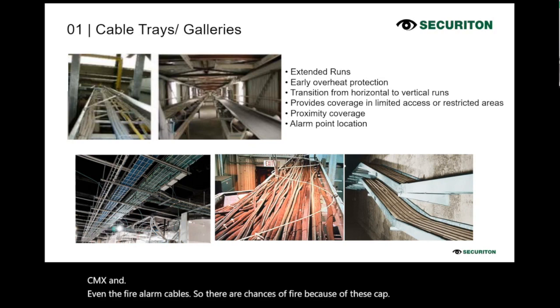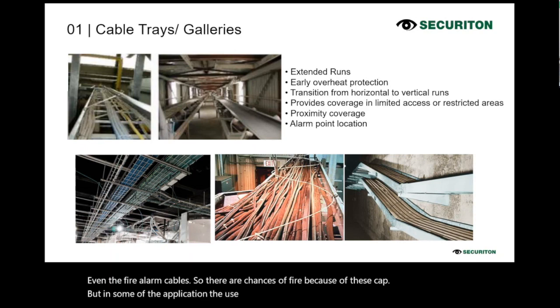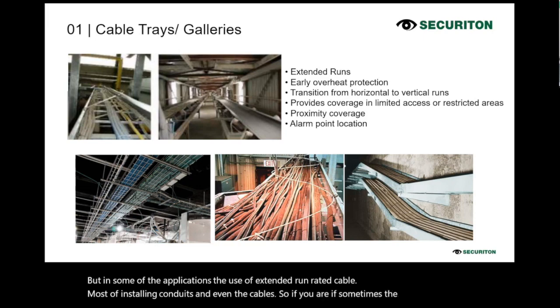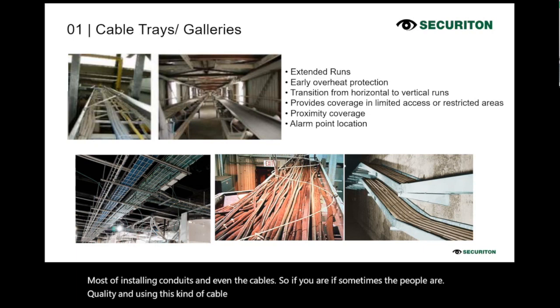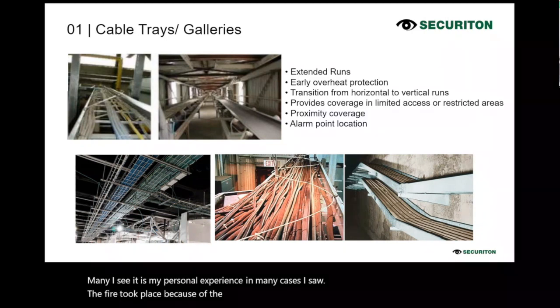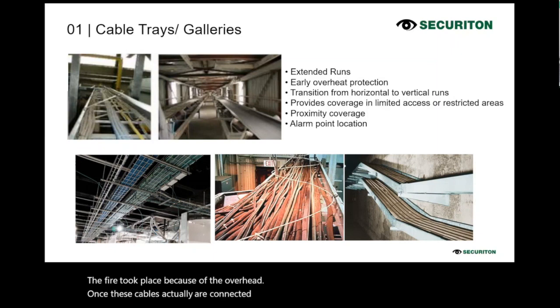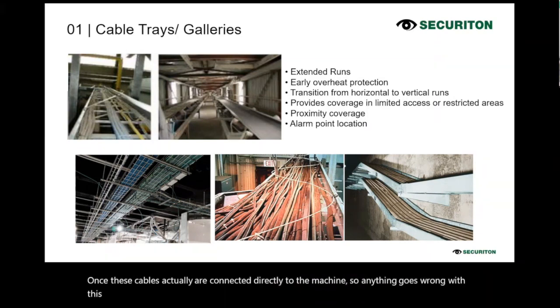In some of the applications, extended run rated cable is used to save the cost of installing conduits and even the cables. Sometimes people compromise on quality and use this kind of cable, and many times the fire took place because of the overheat. Once these cables are connected directly to the machine, if anything goes wrong with the cable, the machine will also come into fault.